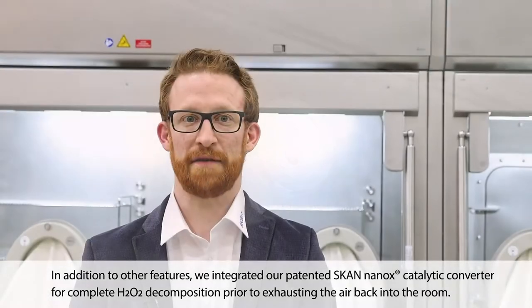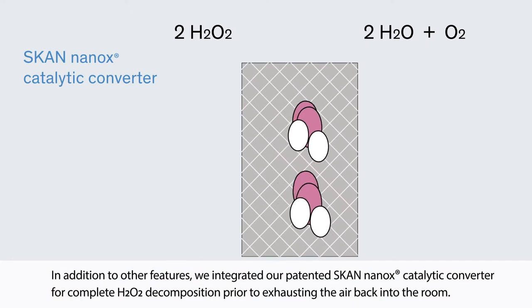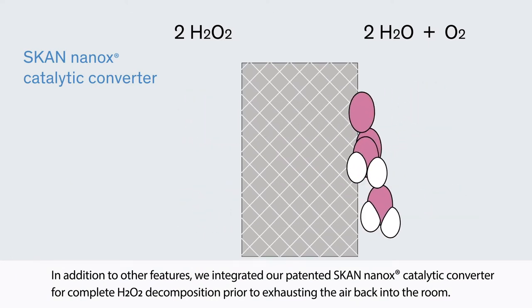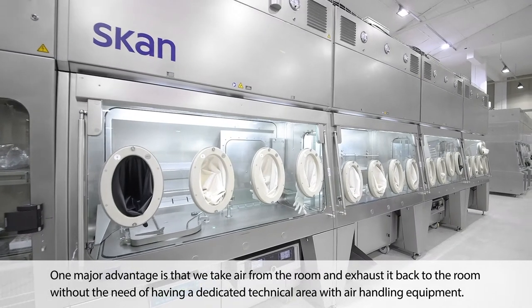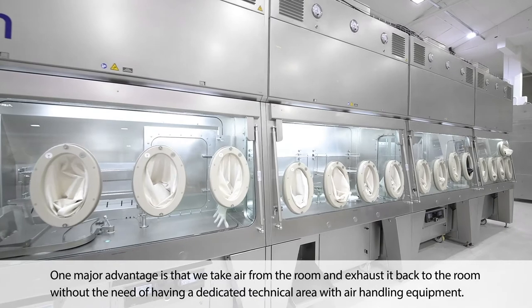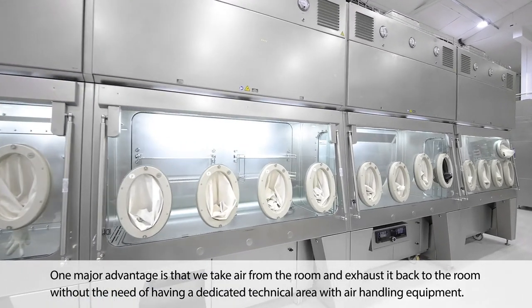In addition to other features, we integrated our patented SKAN nanox catalytic converter for complete H2O2 decomposition prior to exhausting the air back into the room. One major advantage is that we take the air from the room and exhaust it back to the room without the need of having a dedicated technical area with air handling equipment.